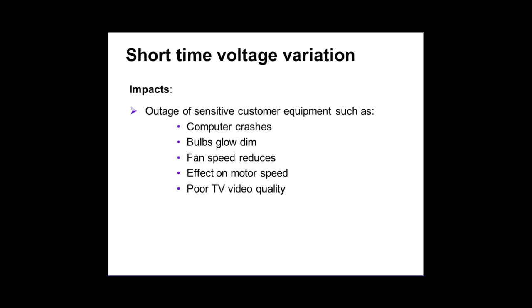Just as a result of that short time voltage variation, this is exactly what you've done to me. Same thing applies to voltage swell. Well, you told me 100% means 220 volts, yes. So you just had an increase of 10%. Now this is an increase to 1.1, or even between 10% and 80%. You know what you have done to me? Oh, mate, it was nothing. It was just half a cycle to 1 minute, whatever. You just damaged a lot of things. The protection system didn't work, just because that was a very short period of time. You even caused a single line to ground fault. You just damaged the insulation material.